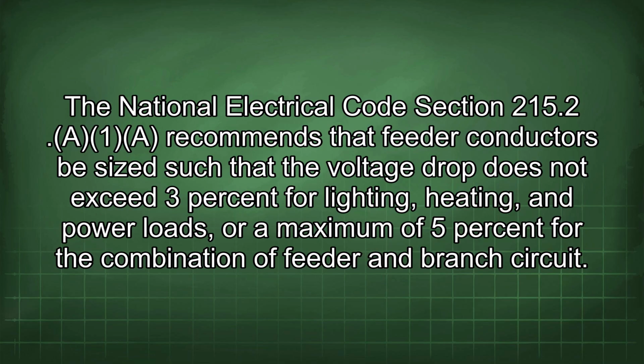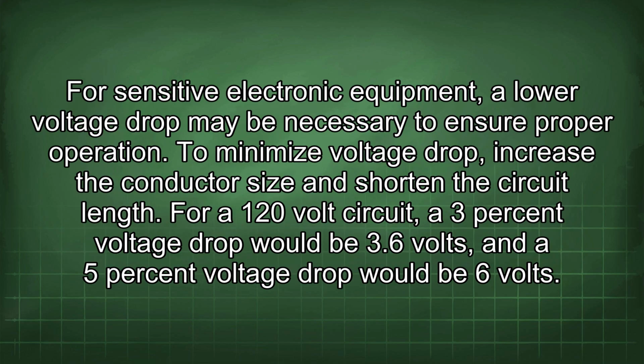The National Electrical Code Section 215.2(A)(1)(A) recommends that feeder conductors be sized such that the voltage drop does not exceed 3% for lighting, heating, and power loads, or a maximum of 5% for the combination of feeder and branch circuit. For sensitive electronic equipment, a lower voltage drop may be necessary to ensure proper operation. To minimize voltage drop, increase the conductor size and shorten the circuit length.